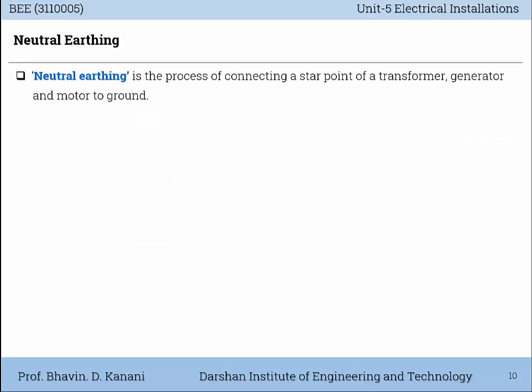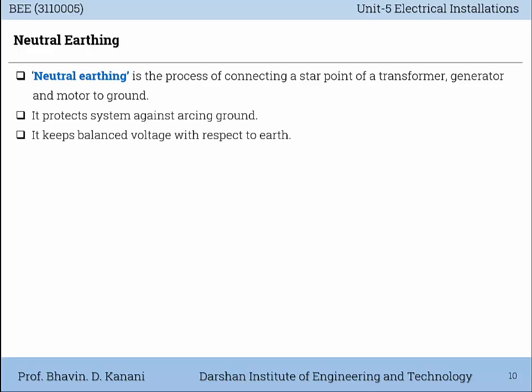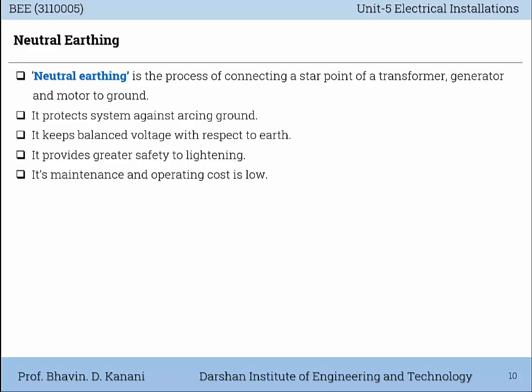Neutral earthing. Neutral earthing is the process of connecting the star point of a transformer, generator and motor to the ground. It protects the system against arcing ground. It keeps a balanced voltage with respect to earth. It provides greater safety against lightning. Its maintenance and operating cost is low. It is reliable in operation.